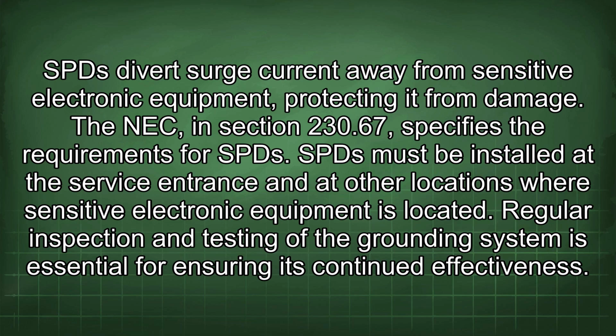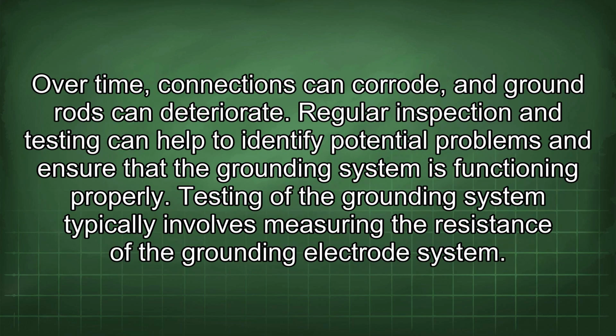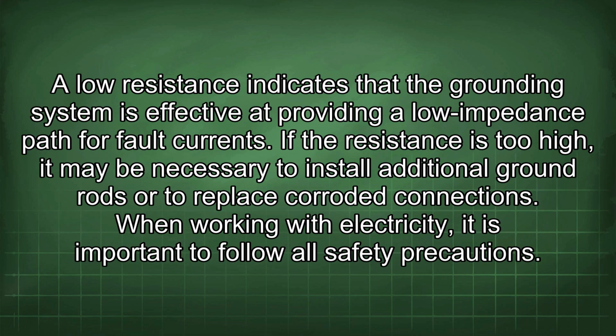Regular inspection and testing of the grounding system is essential for ensuring its continued effectiveness. Over time, connections can corrode and ground rods can deteriorate. Regular inspection and testing can help to identify potential problems and ensure that the grounding system is functioning properly. Testing of the grounding system typically involves measuring the resistance of the grounding electrode system. A low resistance indicates that the grounding system is effective at providing a low impedance path for fault currents. If the resistance is too high, it may be necessary to install additional ground rods or to replace corroded connections.